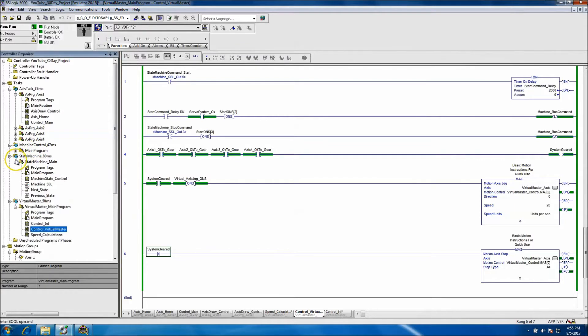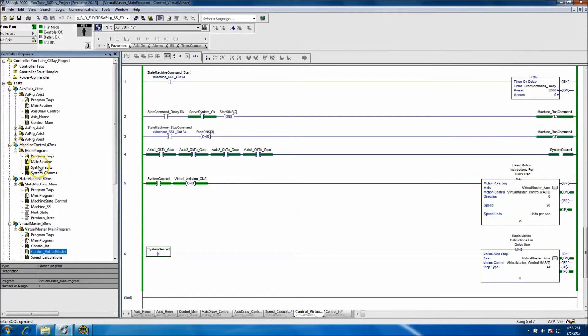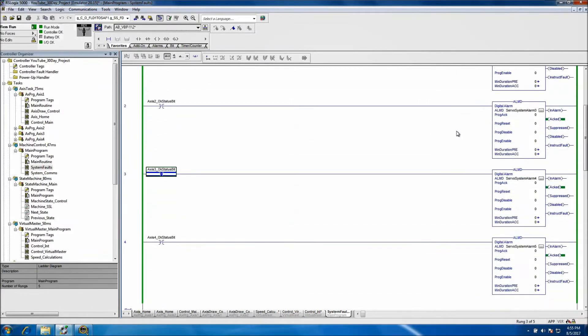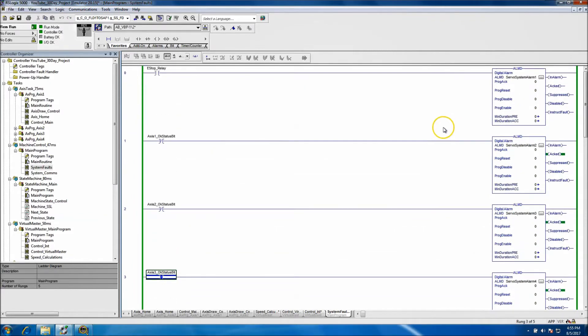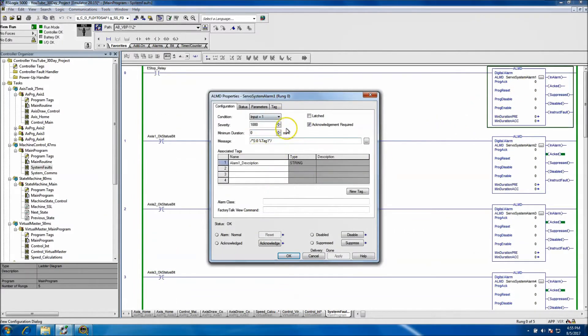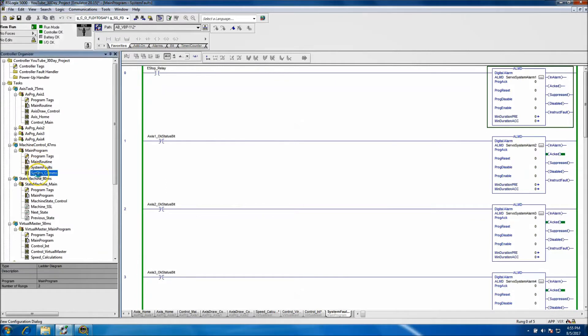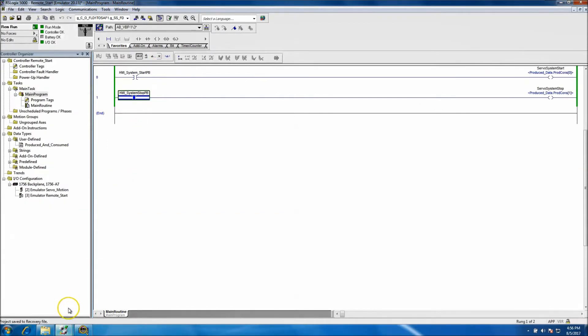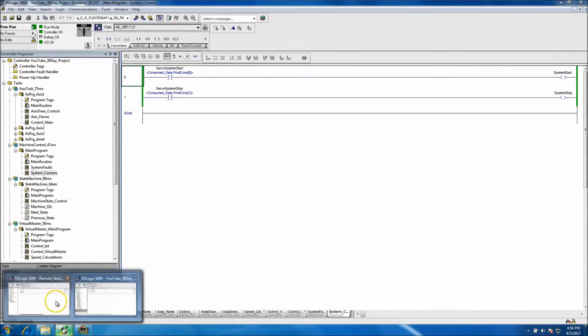We have the state machine and the fault state machine. In the fault screen, we have every fault that would shut down the state machine. We added the ALMD instruction, which gives a digital alarm to the alarms and event summary on the HMI. We also did system comms, because we had a remote system with another PLC doing the starts and stops of our system.